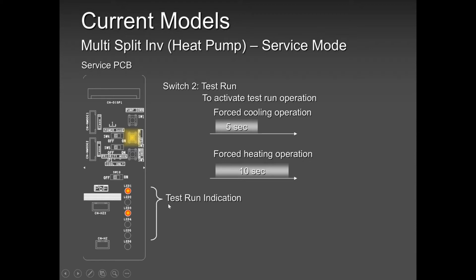The only time I tell guys not to use test run is on a brand new installation, commissioning. I always tell my guys, when you're commissioning the system, run 1 unit at a time. When you're done with your installation, you release the gas, everything is up and fine, no problem, you're ready to start. Don't run it in test run, please. Run one unit, make sure it's running for 5 minutes, you're getting good cooling, and the other units are switched off by the remote controller. You're happy, switch it off, go to the next, run it for 5 minutes, others are off, move to the third unit, fourth and fifth. So run one unit at a time, please, just to make sure that you do not cross your wires.